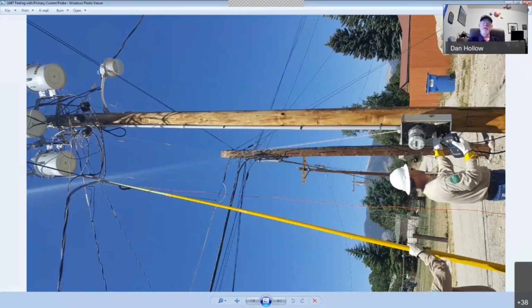What the guy on the left is doing, where you can only see his arm in this particular picture, is moving that high voltage probe from one conductor as it exits the CT to the next conductor, and he's testing the CTs down there at the test switch, looking at that primary current, looking at that secondary current, running the burden and ratio test. One of the things I ran into on this site is that the bracket up there with the 3 CTs on it, they're not necessarily in logical order. When we were out there testing, we found that from left to right, it's not A, B, C. There was no particular rhyme or reason to the way they mounted those CTs.